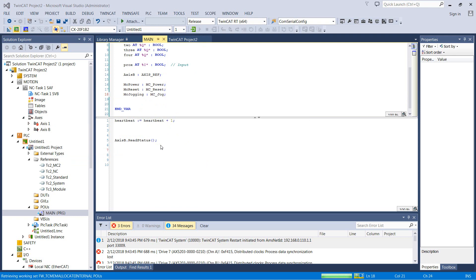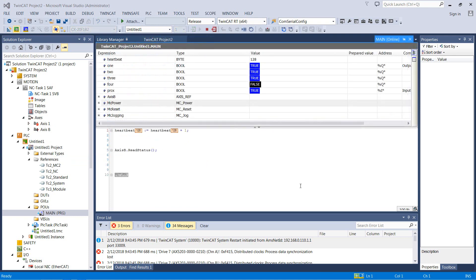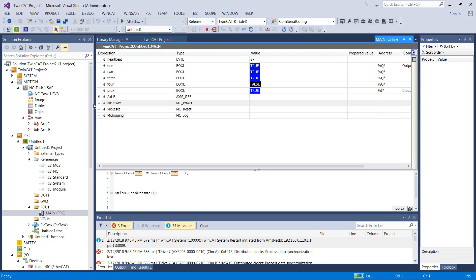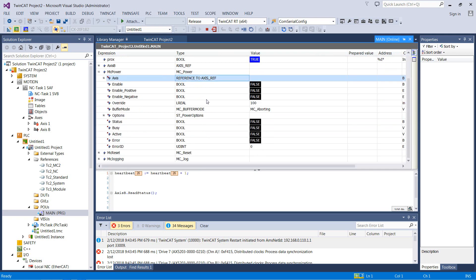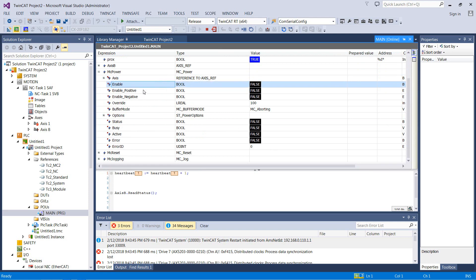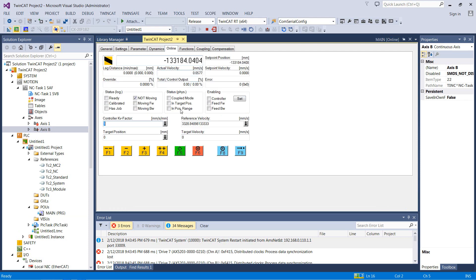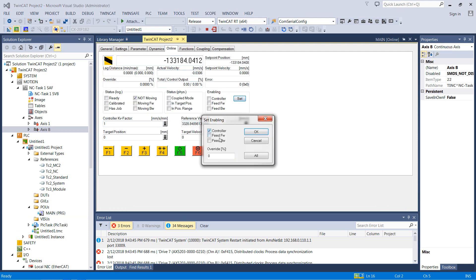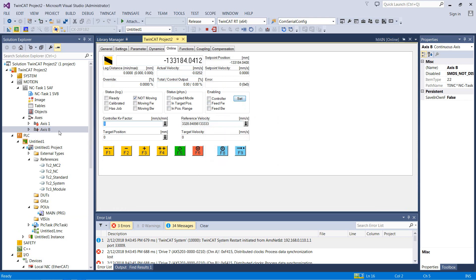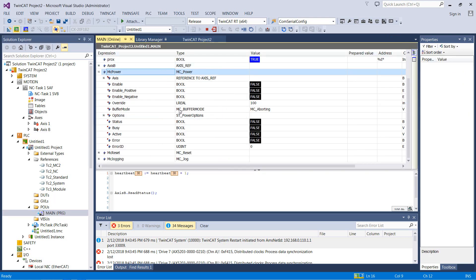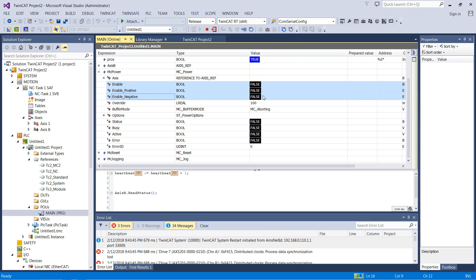Okay, I'm going to give us a little bit of room to work here. MCPower — we've got a reference to the axis, that's pretty standard for all of these function blocks. Enable, enable positive, enable negative. If you remember back on the axis, we had to set this before we did a move. Controller, feed forward, feed backwards — so those are these three here. No big deal, you just do them from the PLC now because we've linked this axis. Override — this is a really nice way to temporarily override the speed of an axis if you wanted to do some testing.